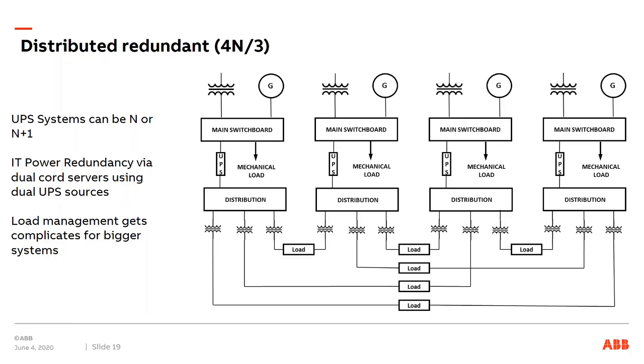So the distributed redundant is also known as 4N/3, or 4 to make 3, or like the catcher, you can add systems. I've seen 8 to make 7, at least on diagrams. And the way this works is that the load is divided between the UPSs. So UPS 1 is sharing its load with UPS 2, 3, and 4. All UPSs are sharing the load, and it's balanced so that all UPSs are equally loaded.